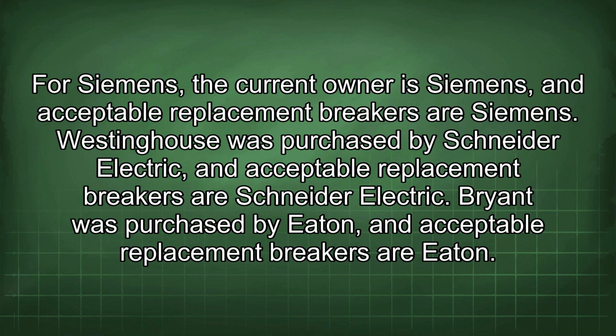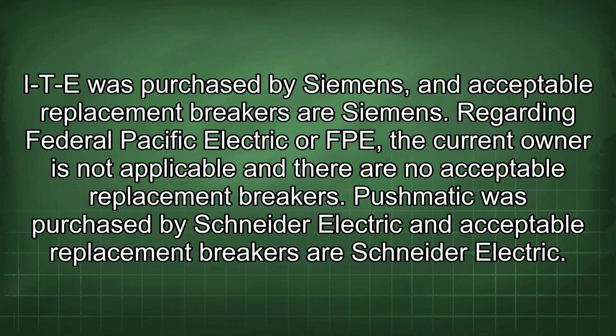Westinghouse was purchased by Schneider Electric and acceptable replacement breakers are Schneider Electric. Bryant was purchased by Eaton and acceptable replacement breakers are Eaton. ITE was purchased by Siemens and acceptable replacement breakers are Siemens. Regarding Federal Pacific Electric or FPE, the current owner is not applicable and there are no acceptable replacement breakers.